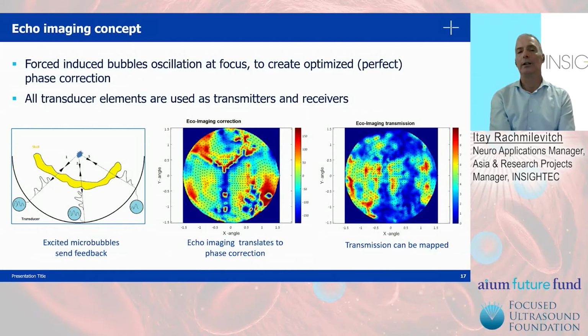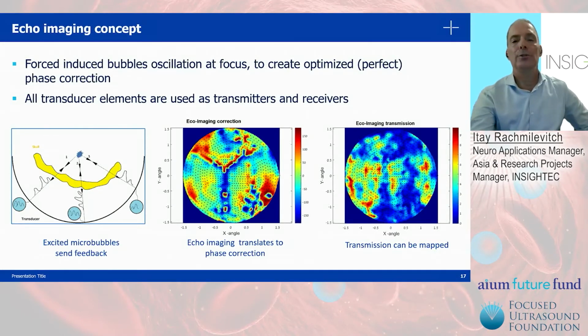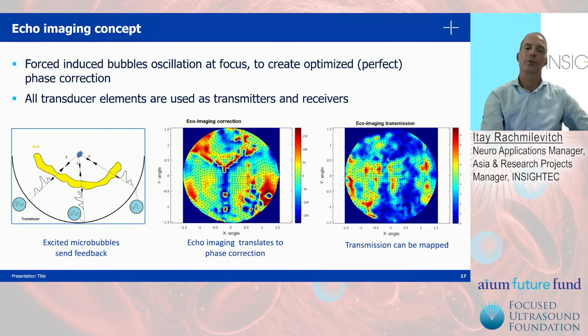We read that, we analyze the phase of each one of the elements, and of course, we can get the phase correction, the optimal phase correction. We reverse it, of course, and use it for optimal focus. After that, we keep this ACT, acoustic correction table, and use it for the ablative treatment that comes after that, which will use not the tens of watts that we have used for this echo imaging, but just the normal acoustic wattage that is needed for the treatment.